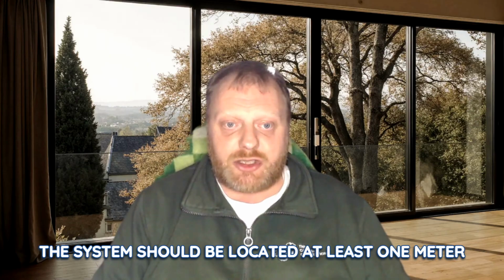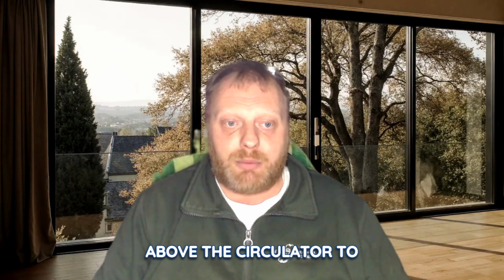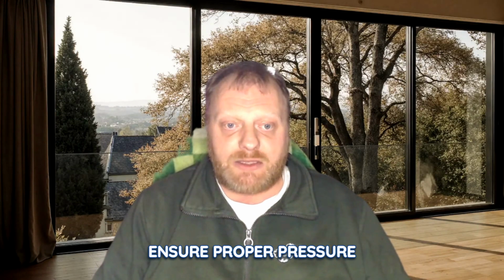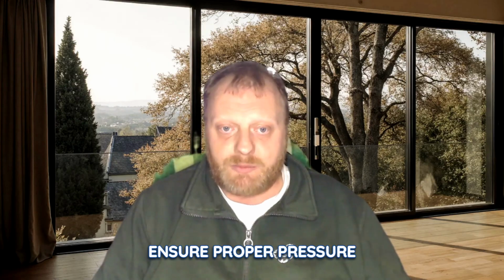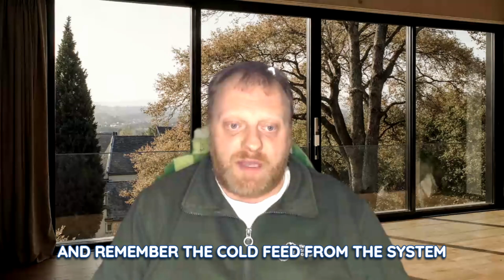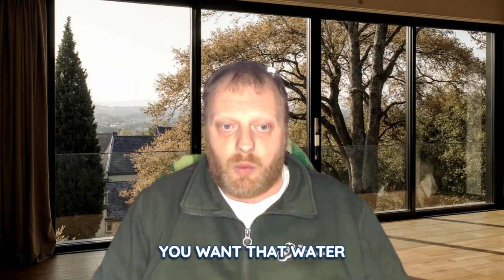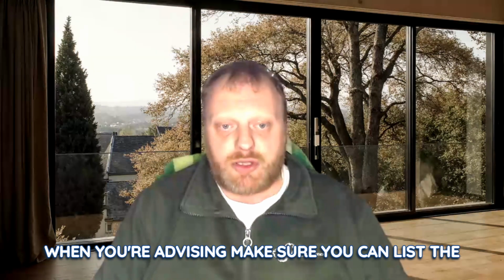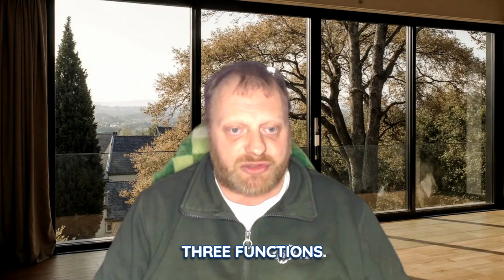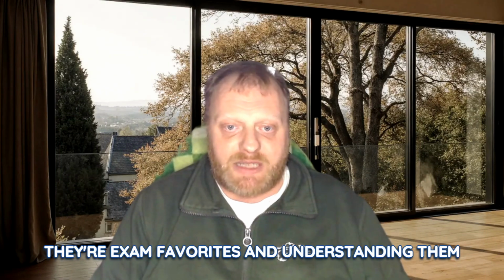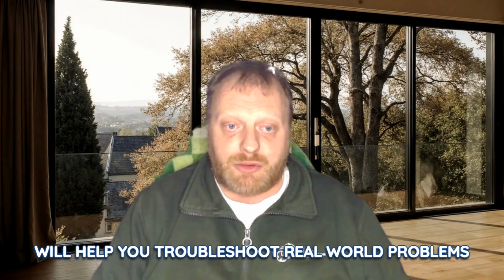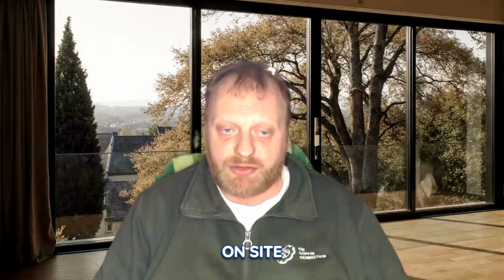The F&E system should be located at least 1 metre above the circulator to ensure proper pressure. And remember, the cold feed from the system should not have any valves. You want that water to flow freely. When you're revising, make sure you can list the 3 functions. They're exam favourites, and understanding them will help you troubleshoot real-world problems on site.